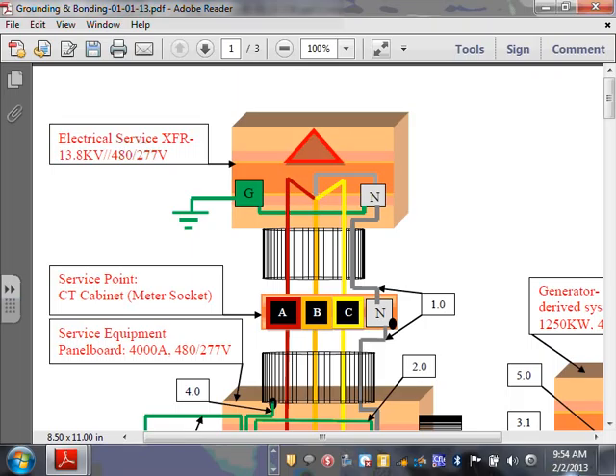If your system is 208, guys, would that be different? No. If your system is 240 single phase 120, would that be different? The only difference is you're going to be pulling 2 conductors and a neutral, right? If this system was a 240/120 three-phase system, that's a delta center tap system, right? They give you a 3-phase system. They tap one of the phases to give you the neutral. Your conductors will look exactly the same as this.